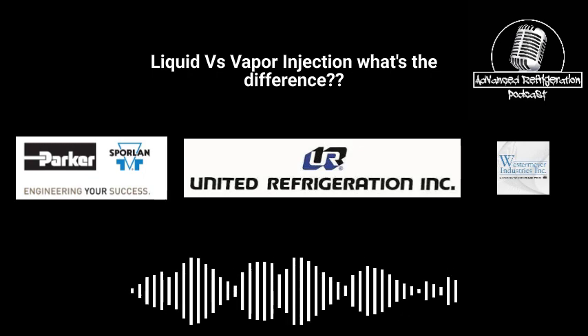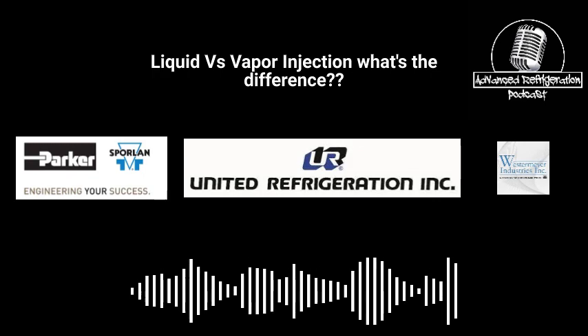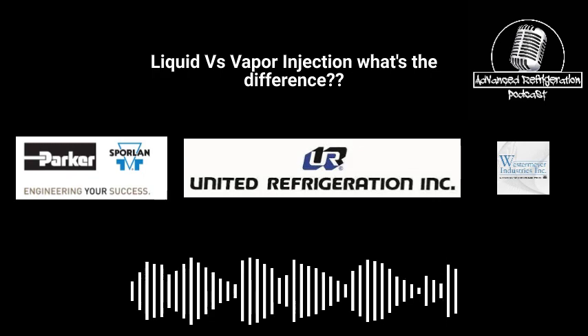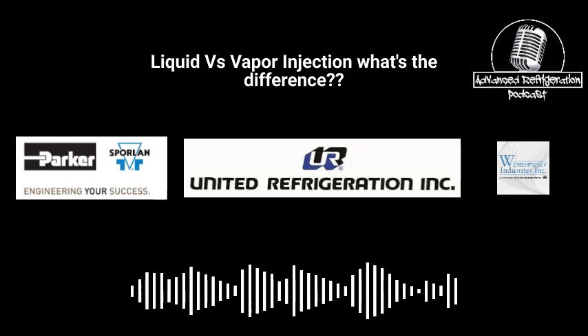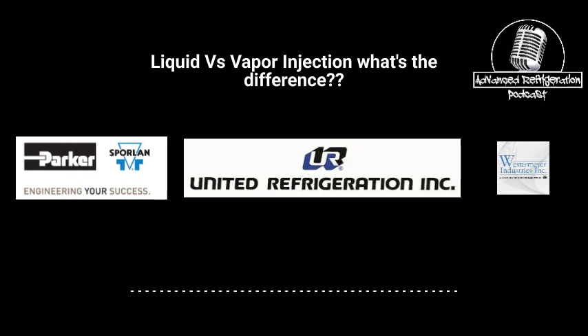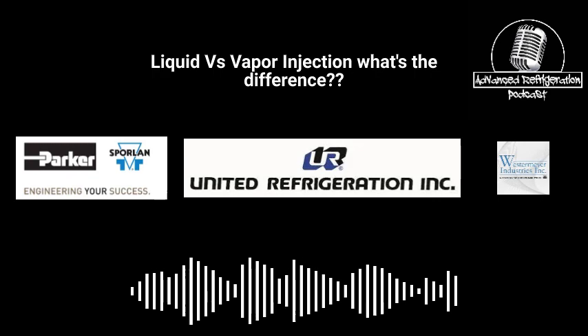I mean, it's injecting, say, 95, 100 degree liquid into like a plus 24 degree suction header or a minus 10 degree suction header. It's going to frost. It's below dew point. It's going to condensate and frost.